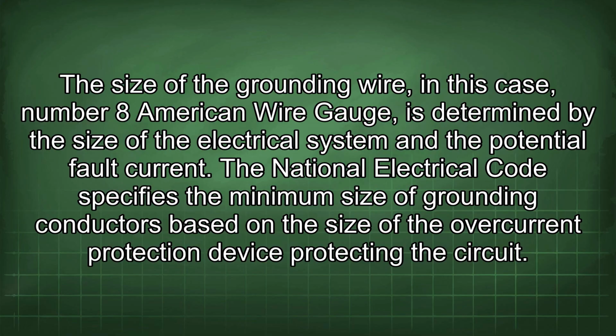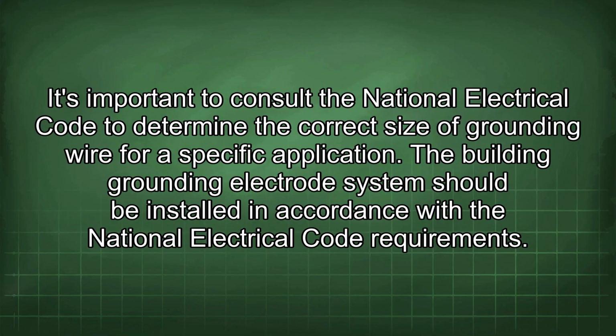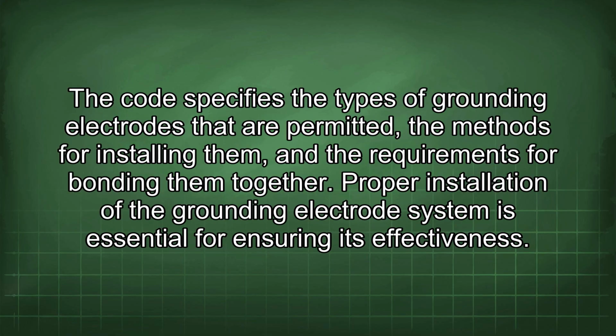The National Electrical Code specifies the minimum size of grounding conductors based on the size of the overcurrent protection device protecting the circuit. It's important to consult the National Electrical Code to determine the correct size of grounding wire for a specific application. The building grounding electrode system should be installed in accordance with the National Electrical Code requirements. The code specifies the type of grounding electrodes that are permitted, the methods for installing them, and the requirements for bonding them together.